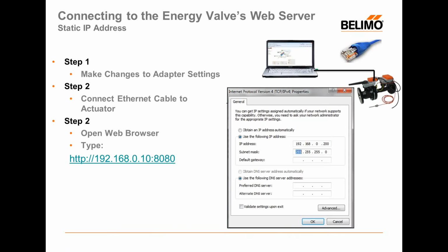So the very first thing you may want to do when you get your energy valve is tie into it to take a look at the settings, maybe see how it's functioning, and see if there are any functional errors that have occurred during startup and commissioning. There are two ways to connect TCP over IP. One is via a static IP address, and what you'll have to do is go into the Network and Sharing Center under Control Panel and set a static IP address in your TCP over IP version 4 settings.